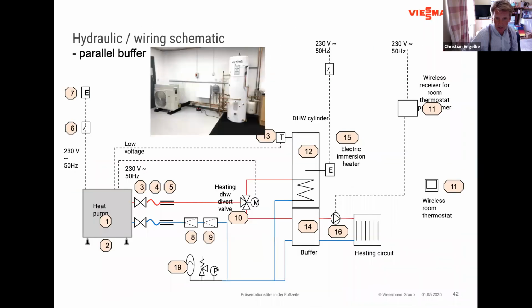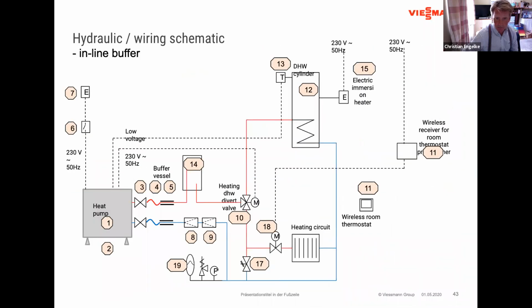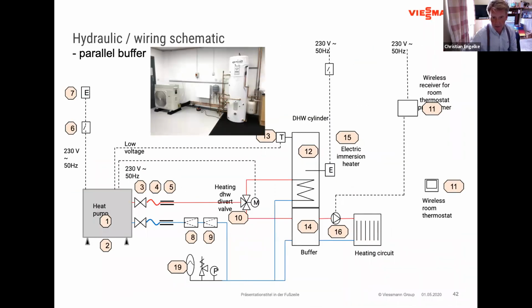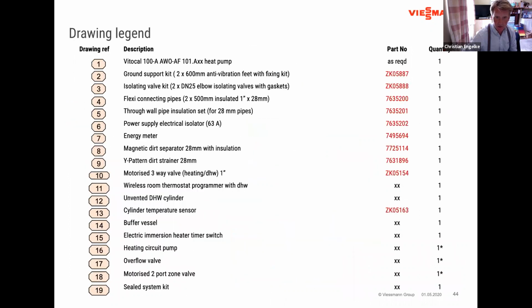Yeah, 65 kilowatt is, I would say, either a very large residential stately home or a commercial installation. We do have commercial installation heat pumps available as well. They are 3-phase, so 400 volts. So the first question is, is 400 volt available? Covering 65 kilowatt with a 230 volt heat pump is difficult.